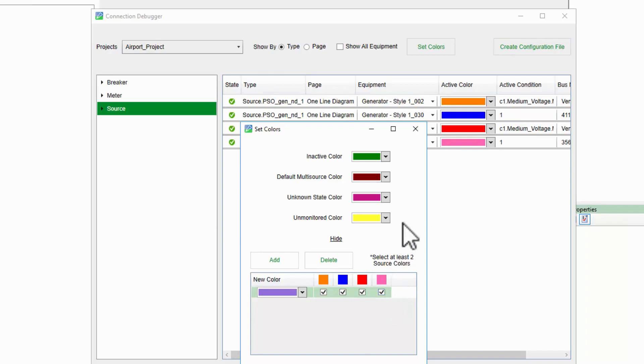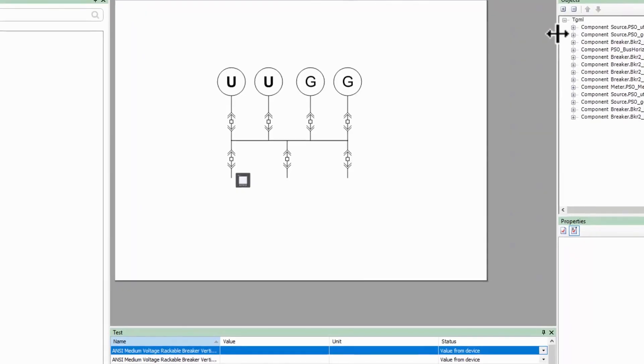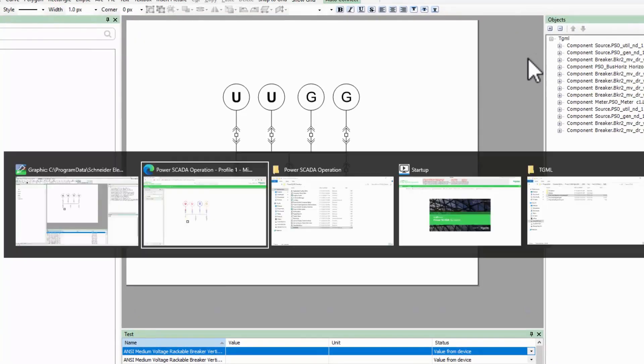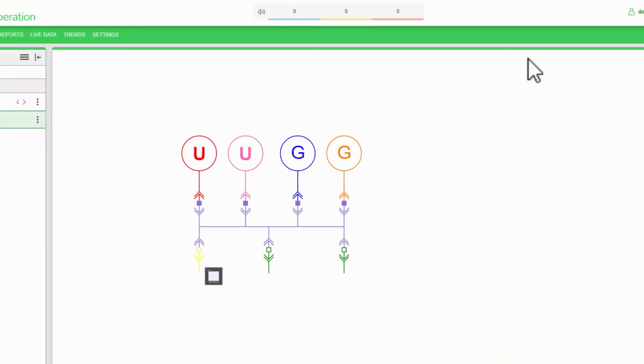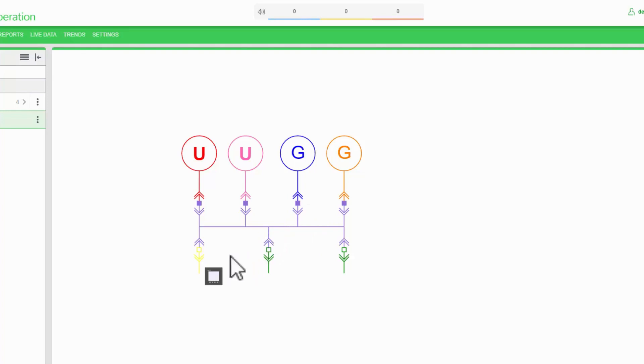I'll close this window and return to the WebHMI where the change has already taken place. As you can see, my main bus has turned violet because all four sources are energizing it. Also, my feeder breaker has turned yellow because my meter is active, but this breaker is open.